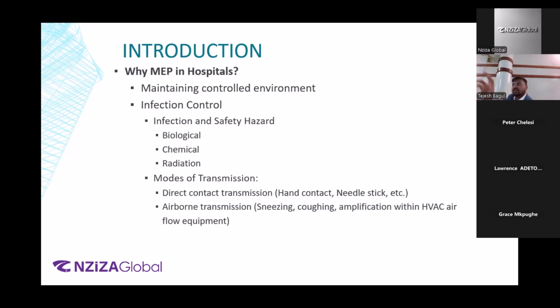Chillers, you'll have a chiller and then you will have a cooling tower. It's called a water-cooled chiller. So with a water-cooled chiller, you will have a cooling tower outside, which will basically bring down the temperature of water that needs to be brought to the condenser of the chiller for heat rejection. Now that cooling tower, on an average building, has a lot of Legionella.